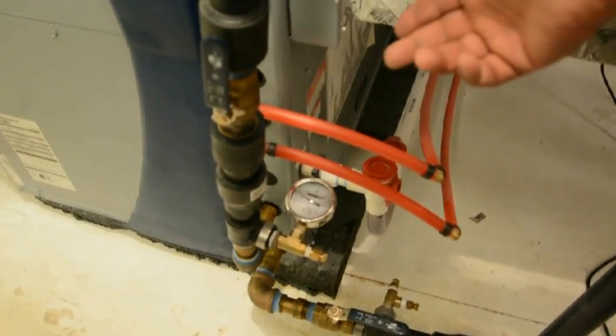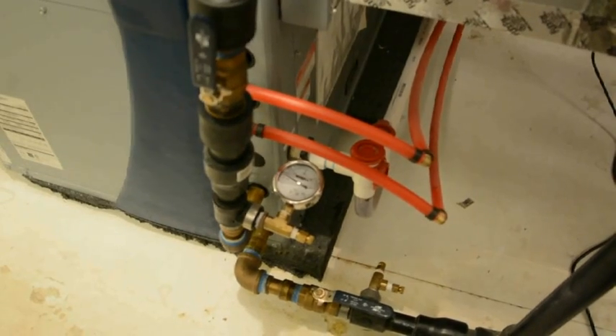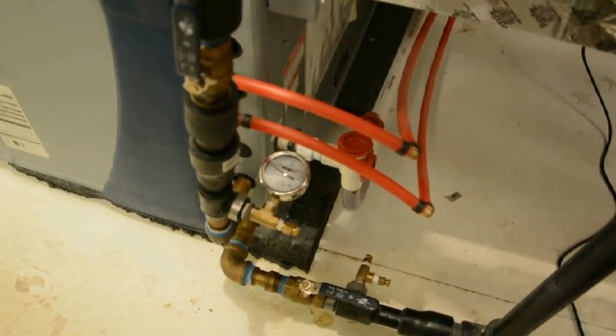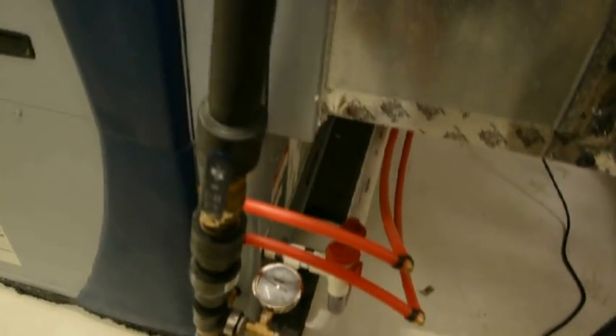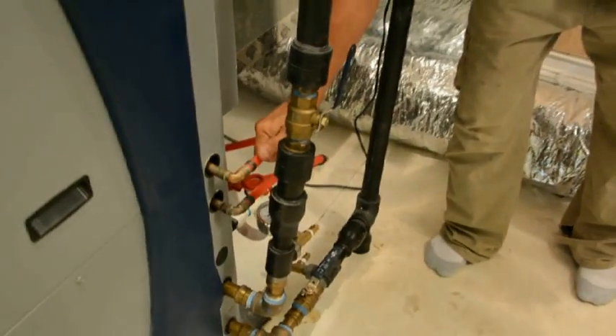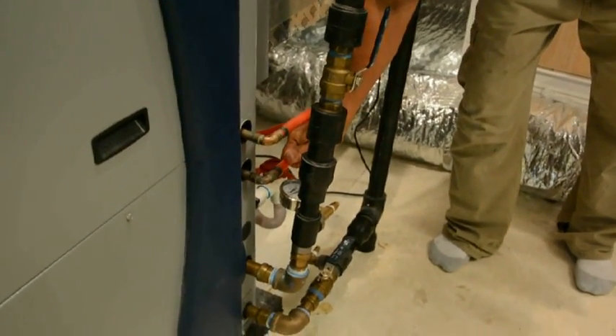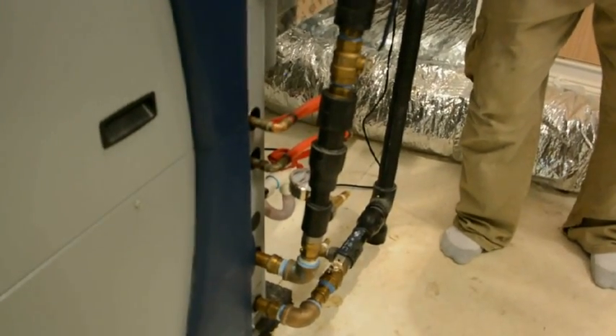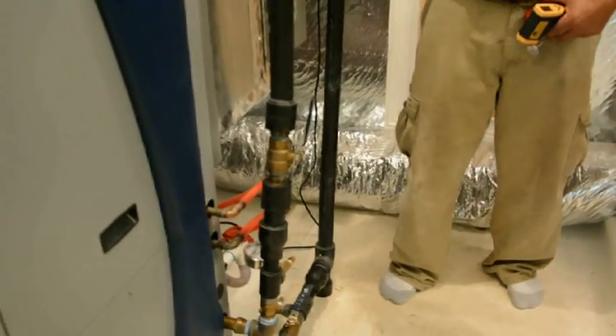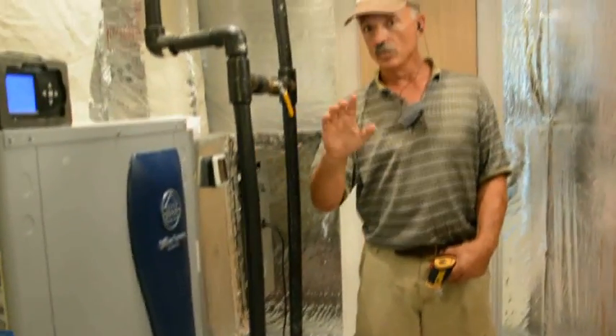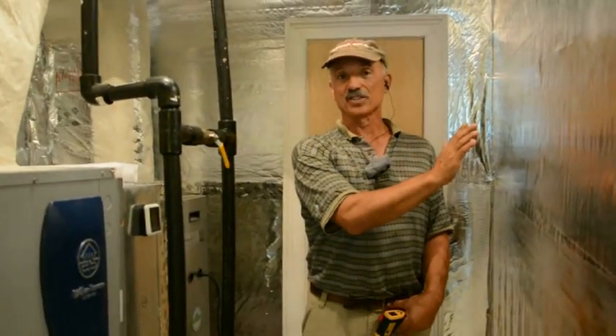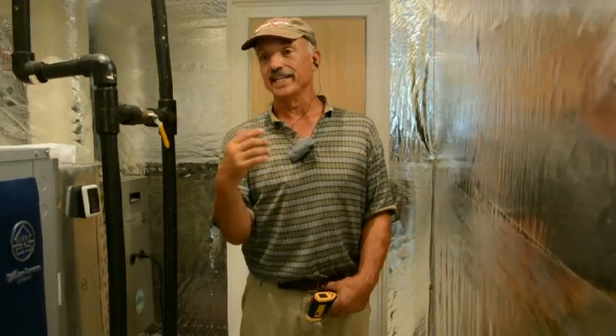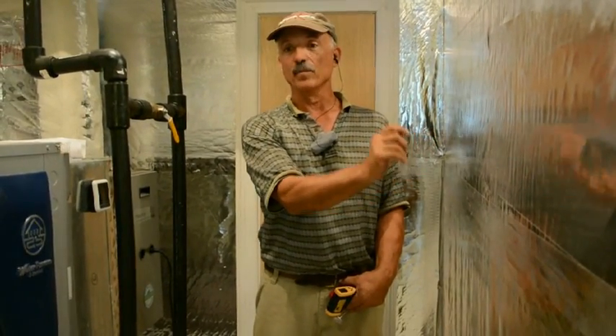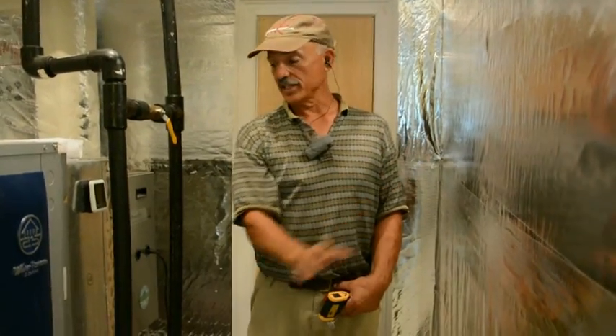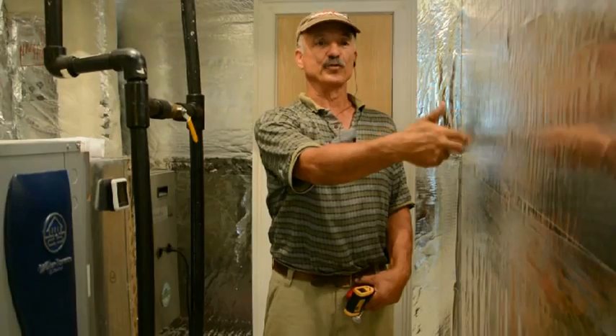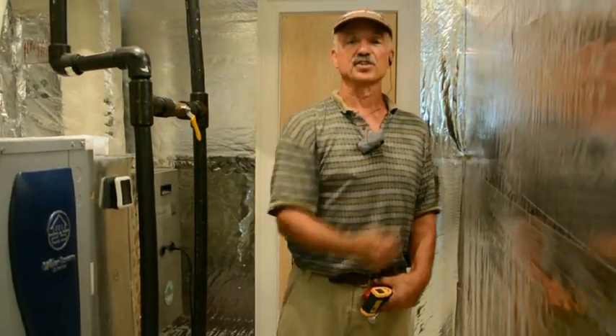We're coming in and out of the house. What happens is that when this compressor comes on, because it's heat pump technology, it's energy transfer - I'm transferring the energy of the house to the water heater. Through these two pipes, you can feel this is warmer, this is cooler; this is coming from the water heater. I'm picking up the heat from the house that's coming through the compressor, that typically would be distributed outside in your house or back into the loop system, because we basically want to take the heat from the house and bring it outside. What we're doing here, which seems to make common sense, is we're taking the heat from inside and putting it into the hot water tank, and when we use the hot water, we get double benefits. So instead of dumping the heat we have to get rid of, or using fossil fuels to heat your hot water, we're taking the heat from your house, and you get to take a shower with it.